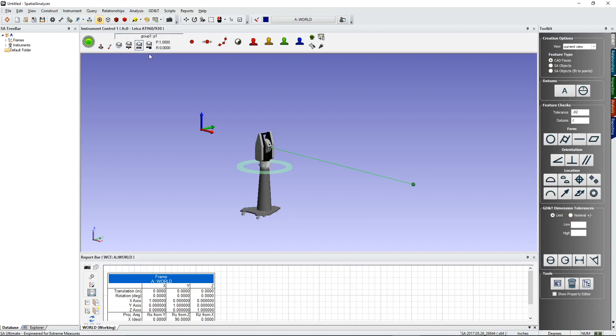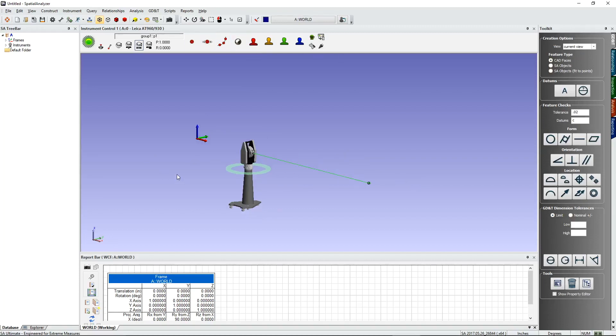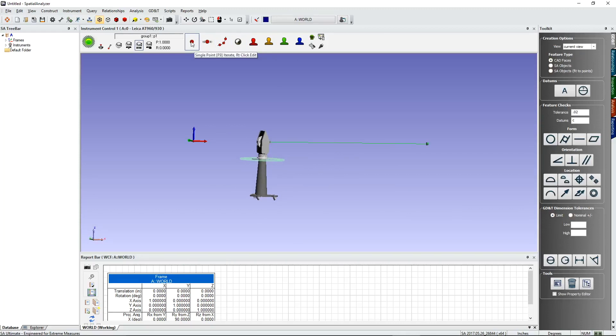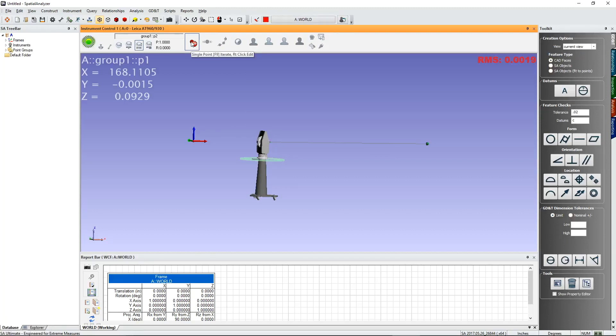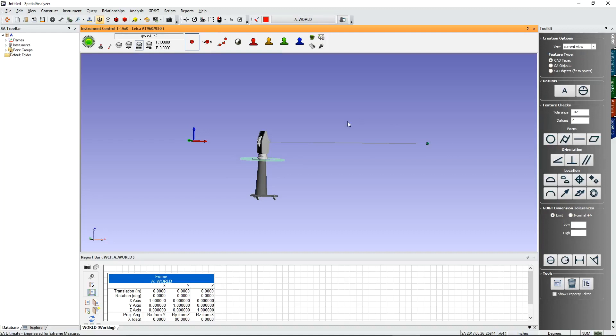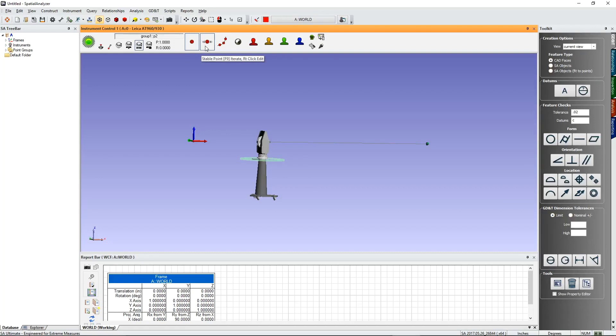Make sure you've selected the correct target before measuring. The final thing to set is the measurement profile, which defines how Spatial Analyzer takes data from the instrument. The four most common profiles are: Single Point, which takes one point when you press the button; and Stable Point, which waits for you to move and stabilize for a set amount of time before automatically triggering a point — great for shooting solo without needing someone else to hit measure.